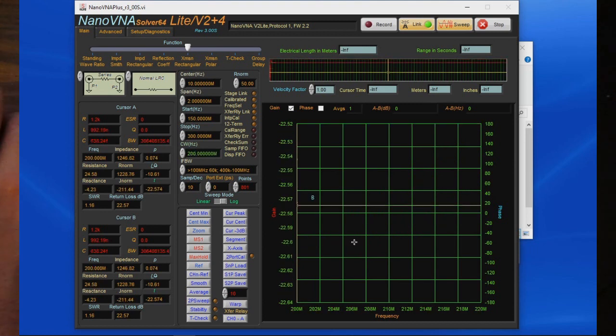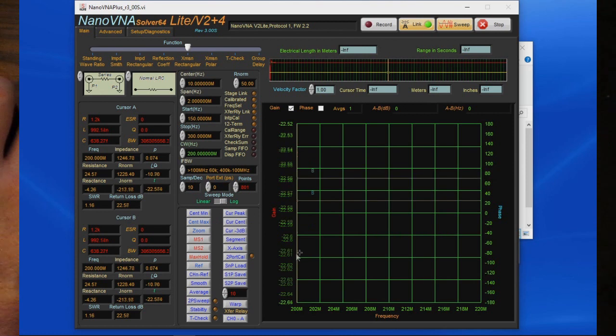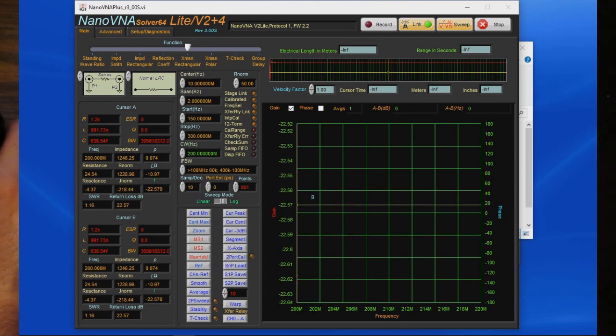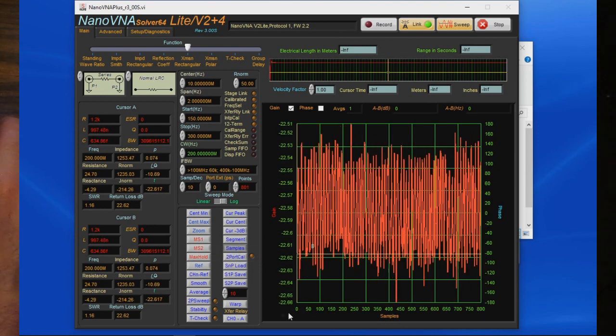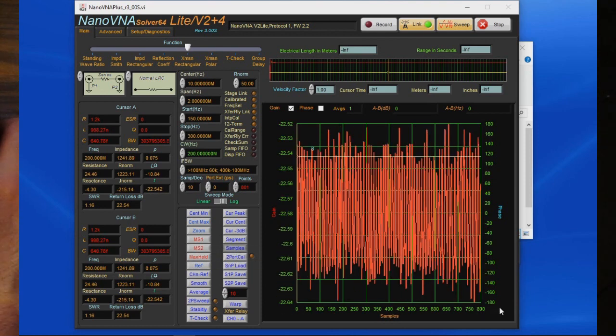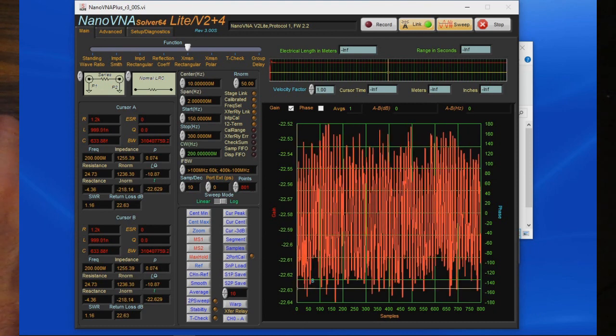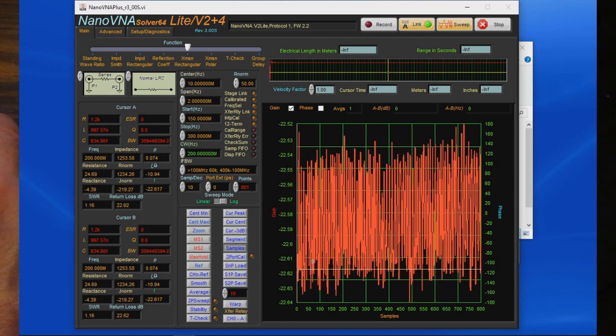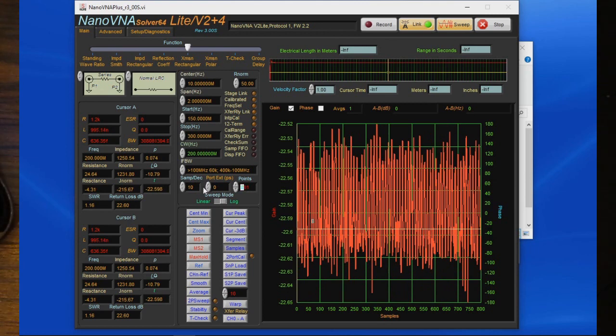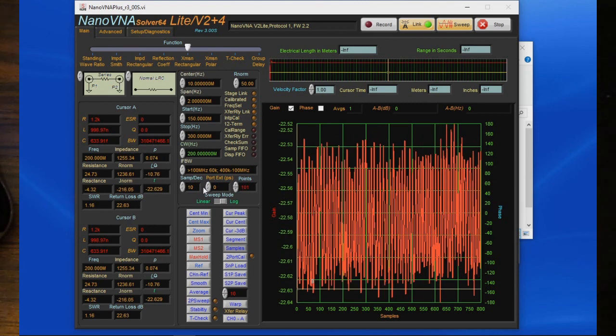So one of the new features of the software again is it allows you to change the axes. So we're only looking at one frequency. You just see a little spike off on the left. What we can do is change the axes from frequency to the data points. We do that by selecting X axes. So now you can see we're looking at sample 0 up to sample 800. Again, we've selected 801 samples. Let's go ahead and drop this back down to 101.